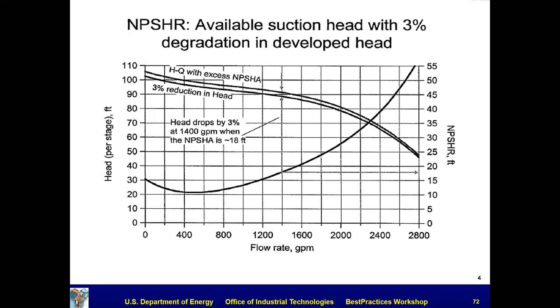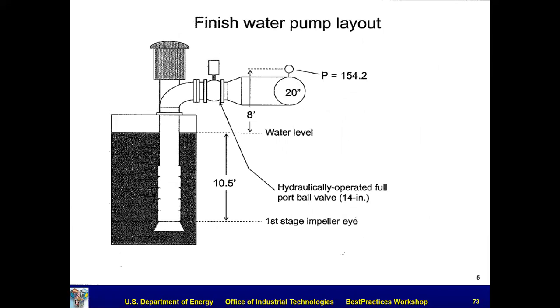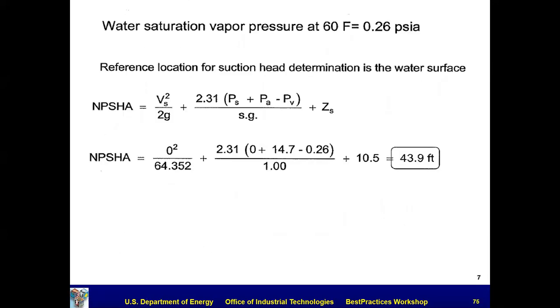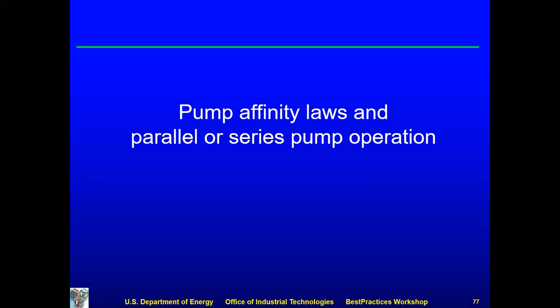So this just shows you a graphic. This shows you a head flow curve with plenty of net positive suction head available. And this is what has happened when I reduce it and operate just at the recommended curve. We've already lost that 3% at the point that they publish. So head drops by 3% at 1400 GPM when NPSHA is approximately 18 feet, which is what they're referring to there. So you really want to stay away from that the best you can. I'm going to skip this. Y'all can read over those.